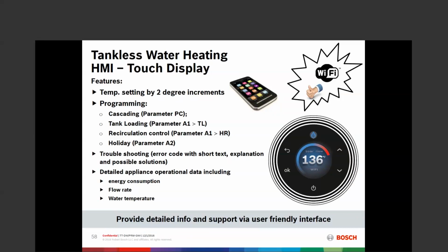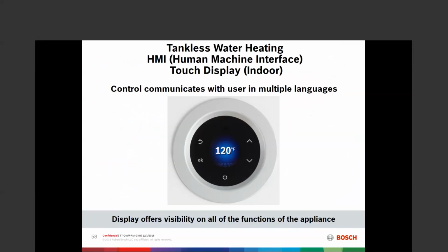If there's a problem with it, it will give an error code. That error code will be an alphanumeric code, and it will also give you a series of 3 or 4 different possible solutions to that error code, or things to look at, right on the display of the unit without breaking out the manual or anything like that. It gives you some ideas where you can possibly correct that, whatever that issue is. Also, while it's operating, it lets you see a lot of the operational data, including your inlet water temperature. It'll let you see the flow rate, how fast that water is coming in to the unit. It lets you see your stack temperature via the NTC. You can see all of that information as the unit's running.